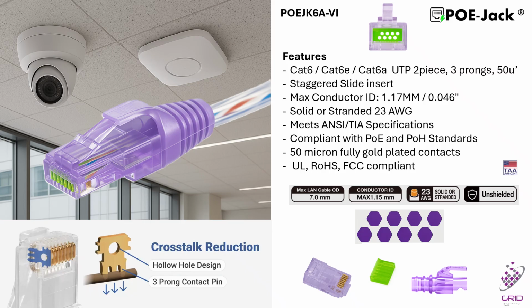Within that connector, there's a green, lime green/yellow staggered sled. The staggered sled keeps the conductors separated prior to full termination, and it makes loading easy. Unlike pass-through connectors, where conductors and insulation pass through and can leave exposed ends, we pass through on the staggered sled, not the connector, because we're worried about shorting or arcing from exposed conductors.